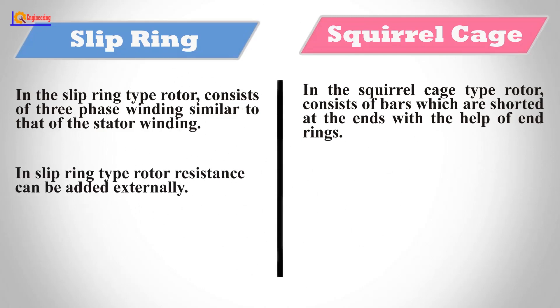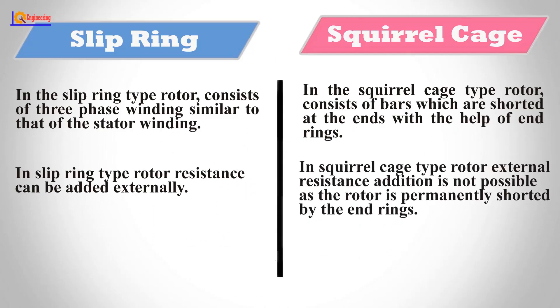In slip ring type rotor, resistance can be added externally. In squirrel cage type rotor, external resistance addition is not possible as the rotor is permanently shorted by the end rings.